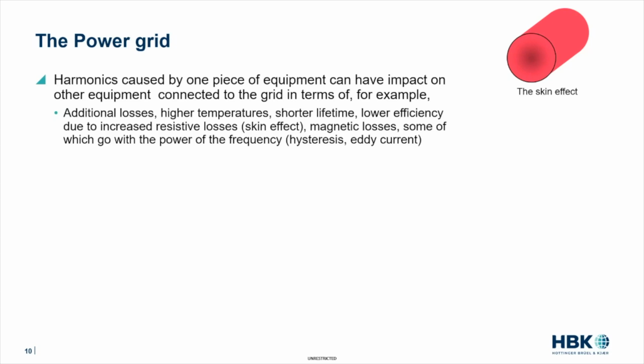So you have two effects. The first effect is that you have a harmonic that you actually don't want, and that harmonic also experiences the skin effect. So the losses that you have because of this harmonic are larger than the losses that you have, relatively speaking, from your fundamental. So that is something that you don't want. That is one of the causes of additional losses caused by harmonics.